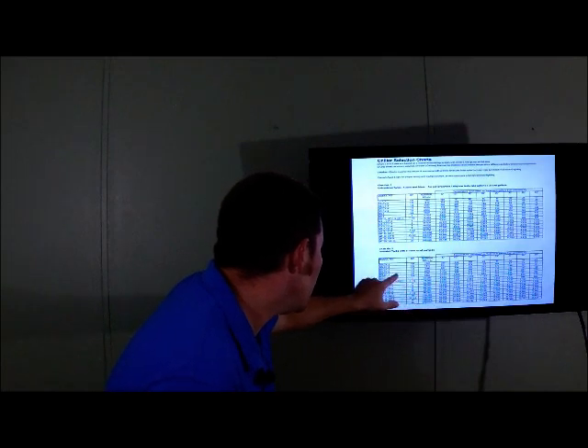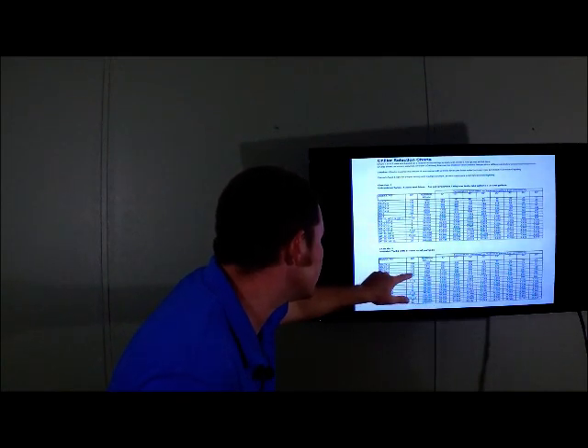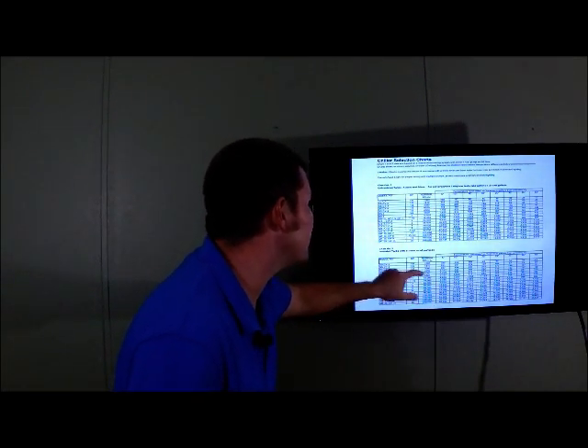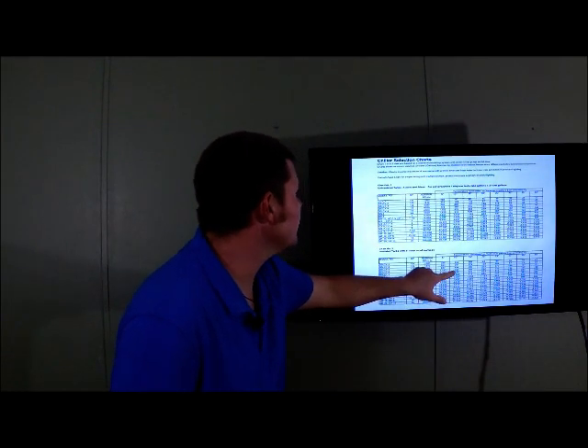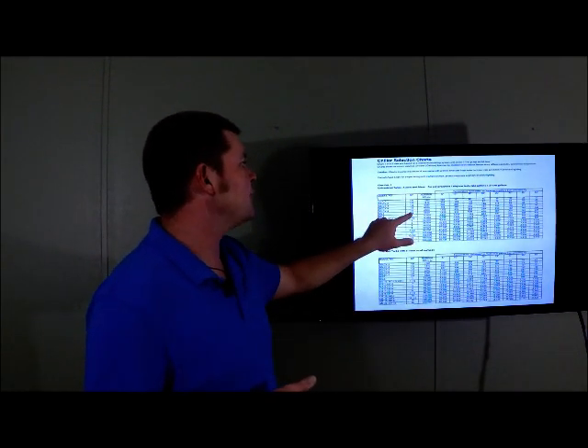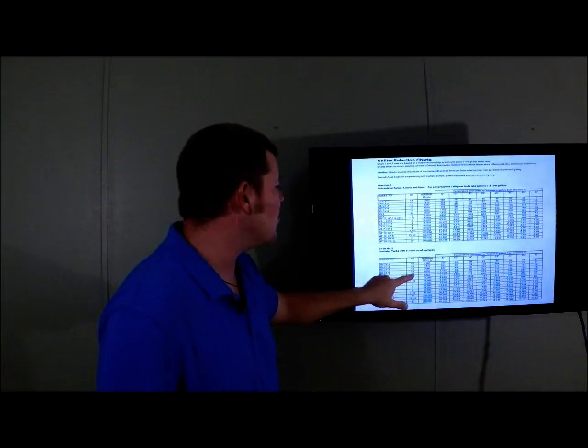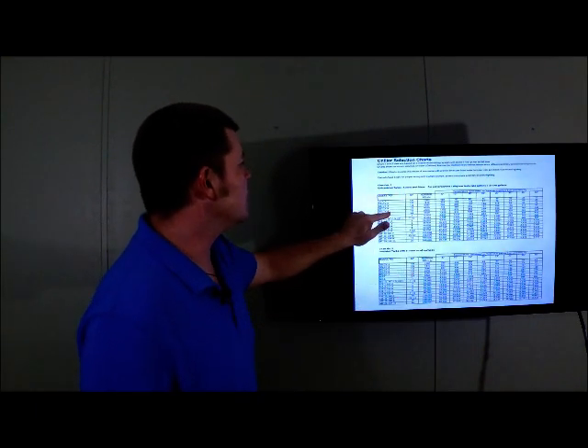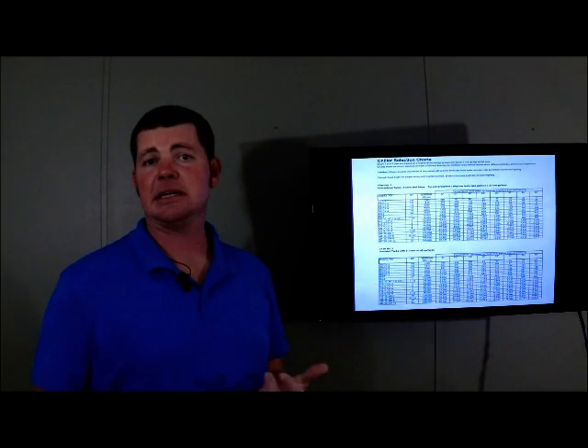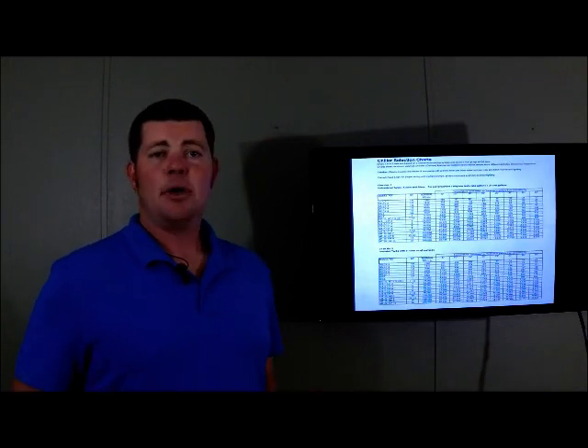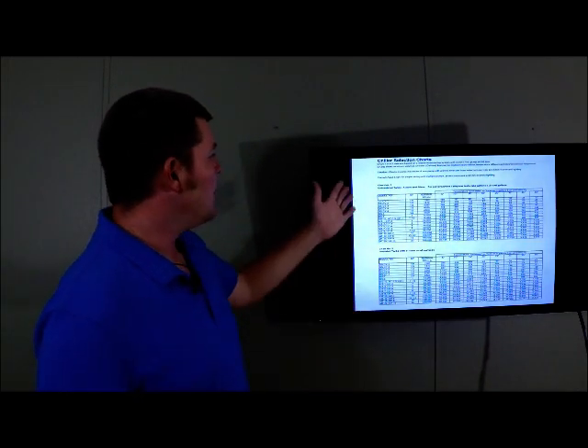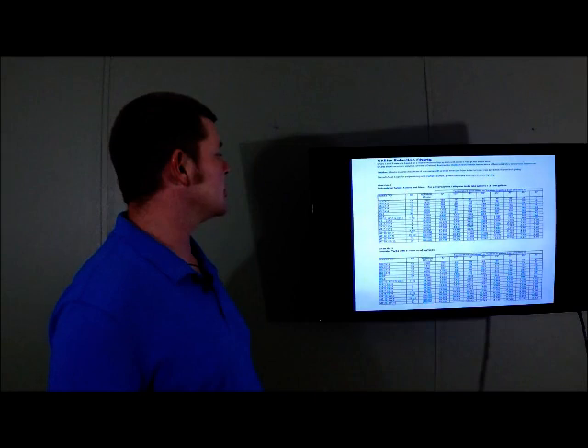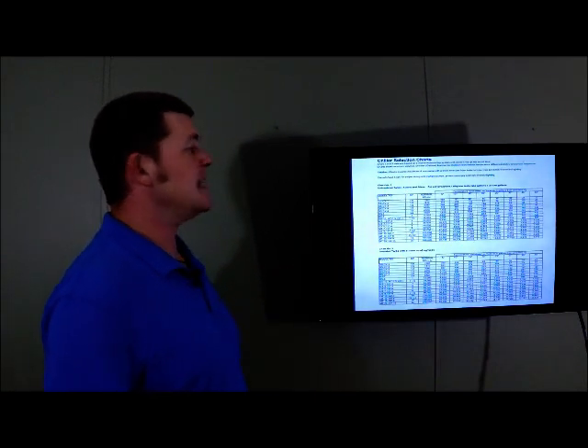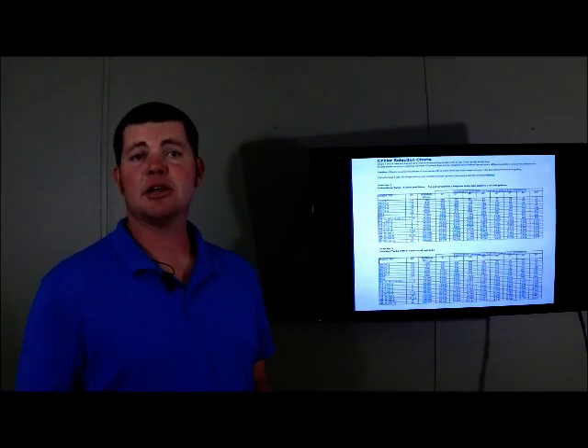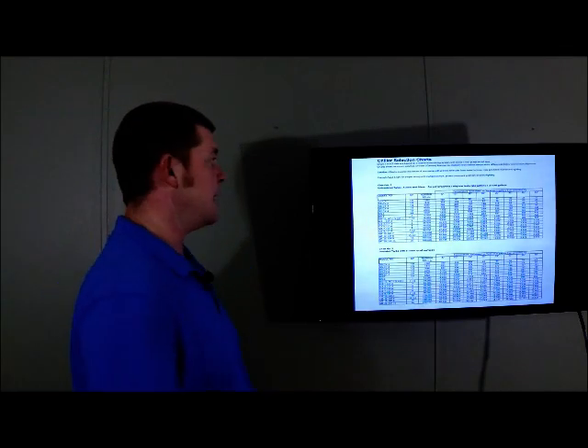The next smallest one, instead of half horsepower, the third horsepower does 583. So we could drop from a half to a third horsepower and still have a little bit more chilling function than you're going to get from an uninsulated system. So I hope that demonstrates that well. These are very good charts. There are other charts that I think are even more detailed on their website. So it's aqualogic.com. Go check it out in your free time.